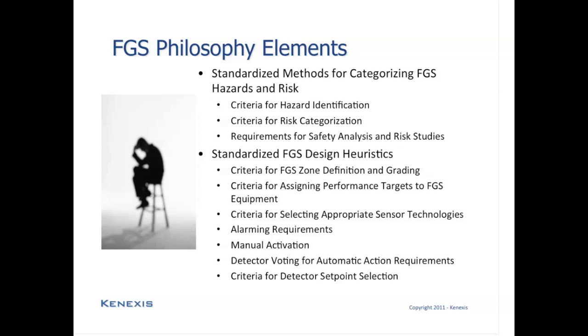And finally, the philosophy is also going to have to list the requirements for what safety analysis is going to be performed. How are those analyses going to be broken down into the various risk studies, and what are the procedures by which those studies will be carried out? Now, in addition to setting up the methods and procedures by which the FGS system is going to be analyzed and designed, there will also be various heuristics or rules of thumb that are going to be used internal to those procedures. For instance, there will be criteria for how to define zones, what the extent of those zones are going to be, and how you may want to grade those zones into different risk categories, which will have different associated performance targets with them.